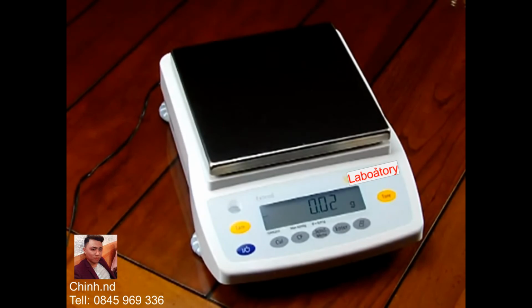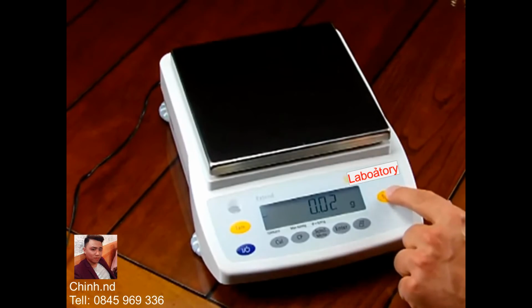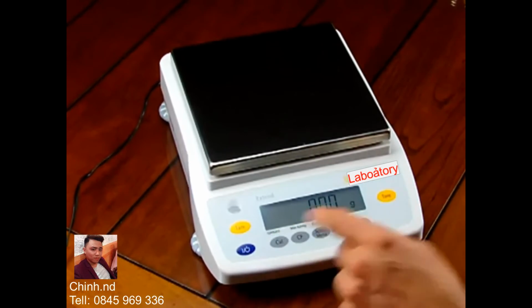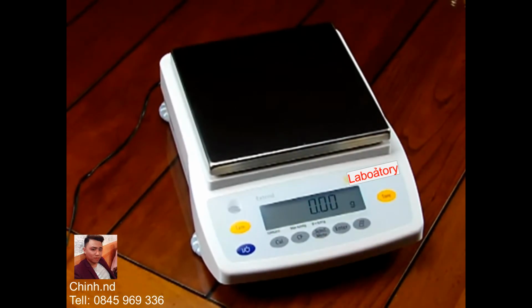We've already gone over the 3-year limited manufacturer warranty and calibration. So again, calibration is simple. Simply pressing the button, you have motorized internal calibration. So our best recommendation for a 0.01 gram balance is right here, the Sartorius GW6202. We highly recommend this balance.